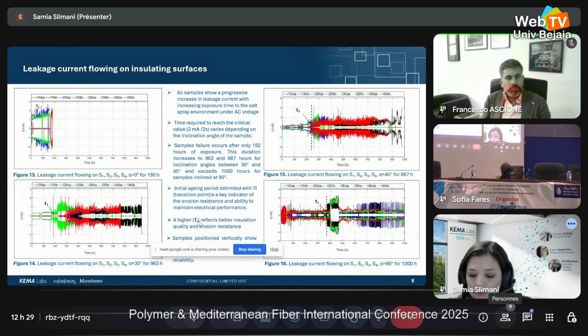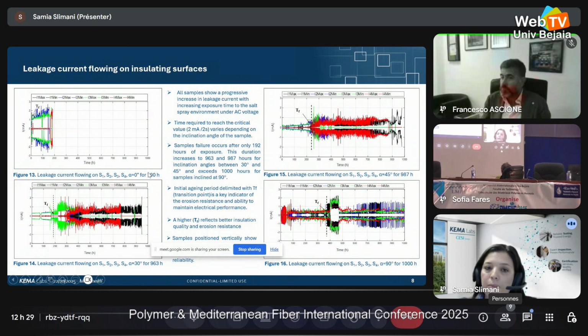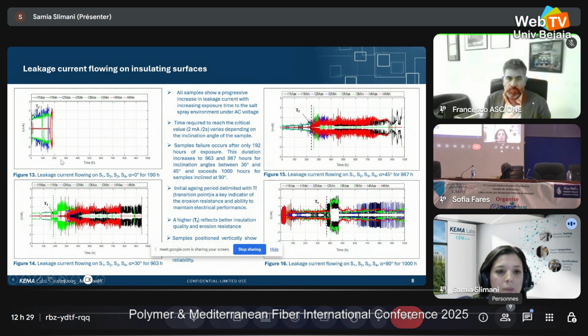The leakage current: these curves show us the leakage current development of all samples for each inclination angle. All samples show a progressive increase in the current with increasing exposure time to the salt fog and under AC voltage. The time required to reach the critical value of 2 milliamp during 2 seconds varies depending on the inclination angle of the sample.